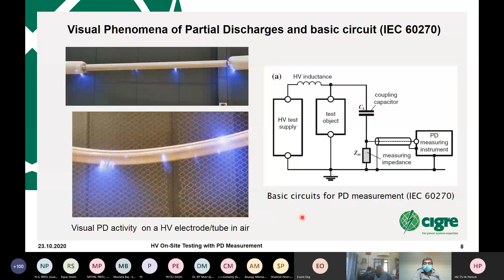The so-called basic circuit, according to the standard, is with a coupling capacitor, which is connected in parallel to the test object, like the transformer or GIS. And then you can evaluate the current which is flowing here to the test object and the coupling capacitor. And then this is analyzed as the PD amplitude. Important, and this is what can be used on site, there are optical effects which we have just seen. There is also heat over time, pressure waves like sound, acoustic in a transformer or GIS, or if you're close to a bushing, then you can hear it. Chemical effects like the production of hydrogen or CO2 in a transformer if the oil is damaged over time, high frequency waves, and so on. So you can pick them up electrically, and this is normally covered with this standard, and then the so-called non-conventional methods, like the high frequency and the ultra high frequency measurements, which are electrical. And of course, the non-electrical ones, these are chemical, optical, and so on.